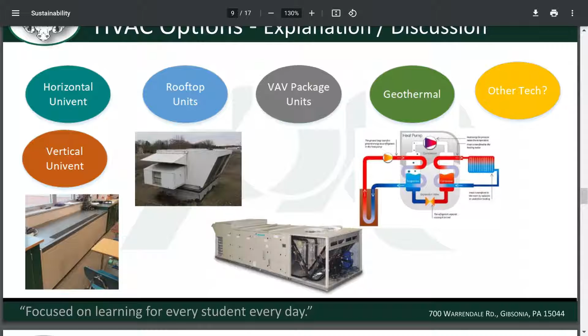Based on our engineer's expertise from Tower, the vertical unit brings air in from the bottom and passes it over the coil the whole way up. It's discharged through the top through flexi duct and can come down in different areas of the room. It dehumidifies better, so we're looking at that as one of our prime ways to install something that makes sense, has a good efficiency rating, and meets our requirements. Next slide, please—any questions so far?